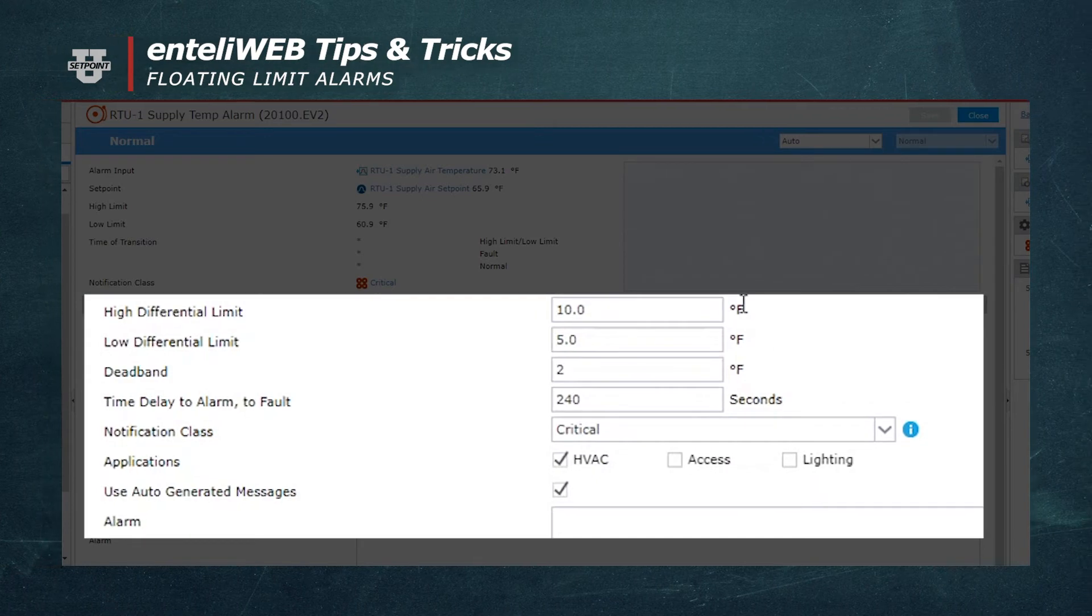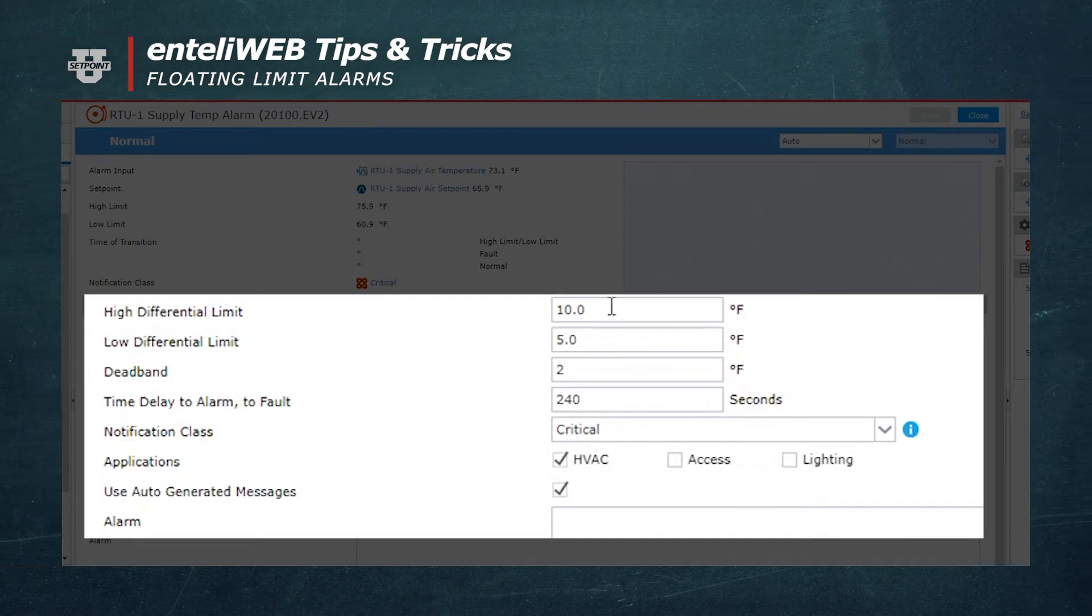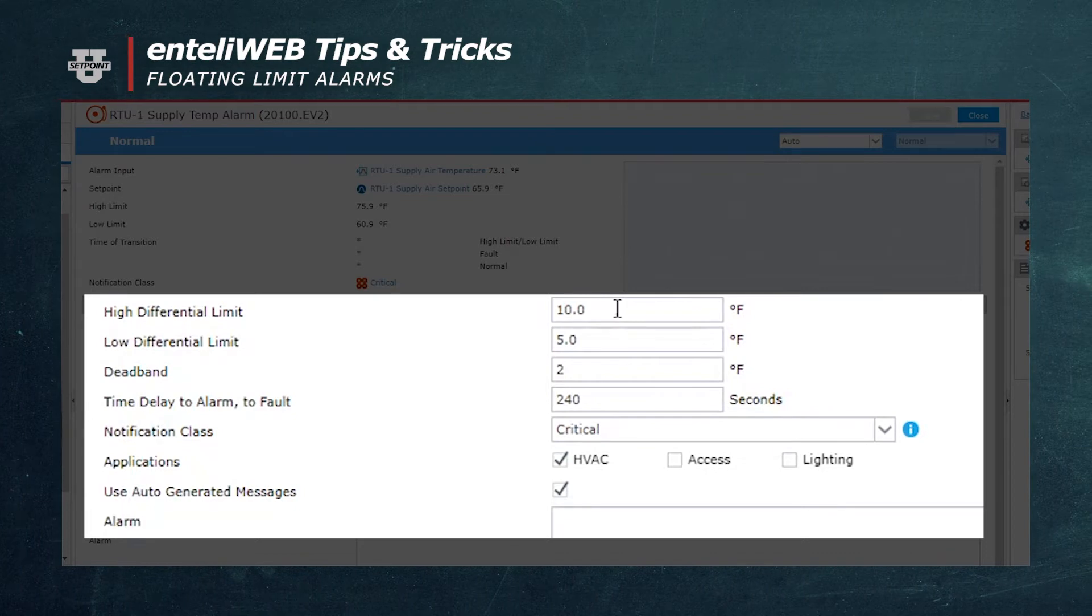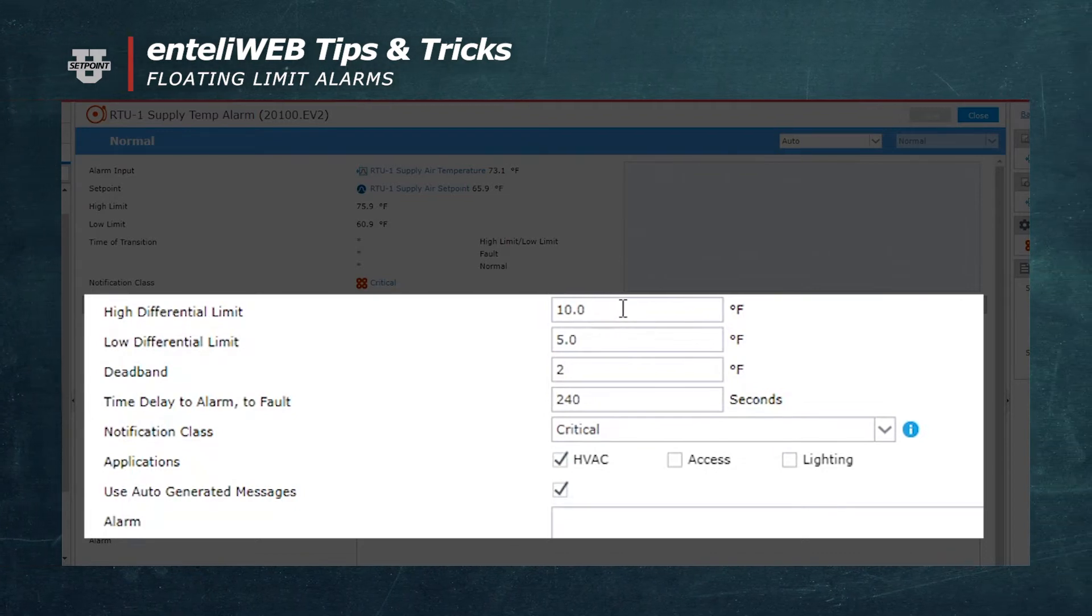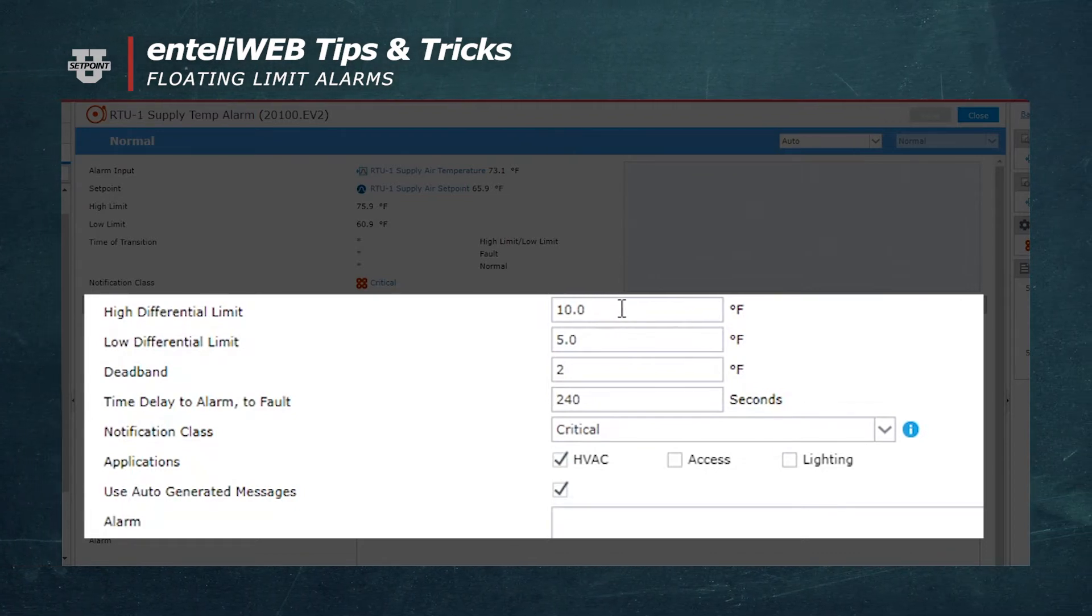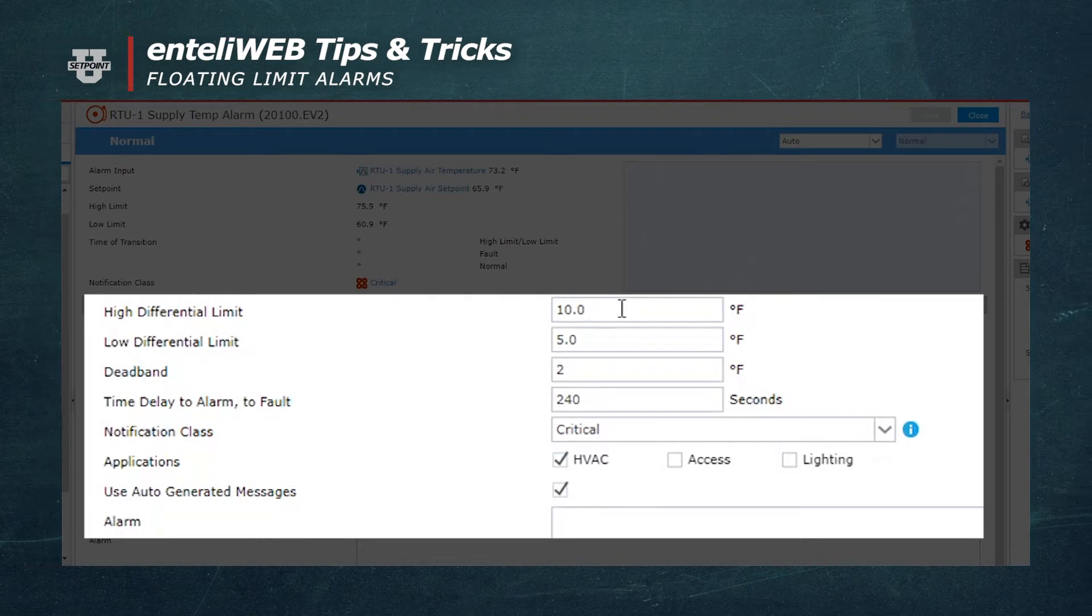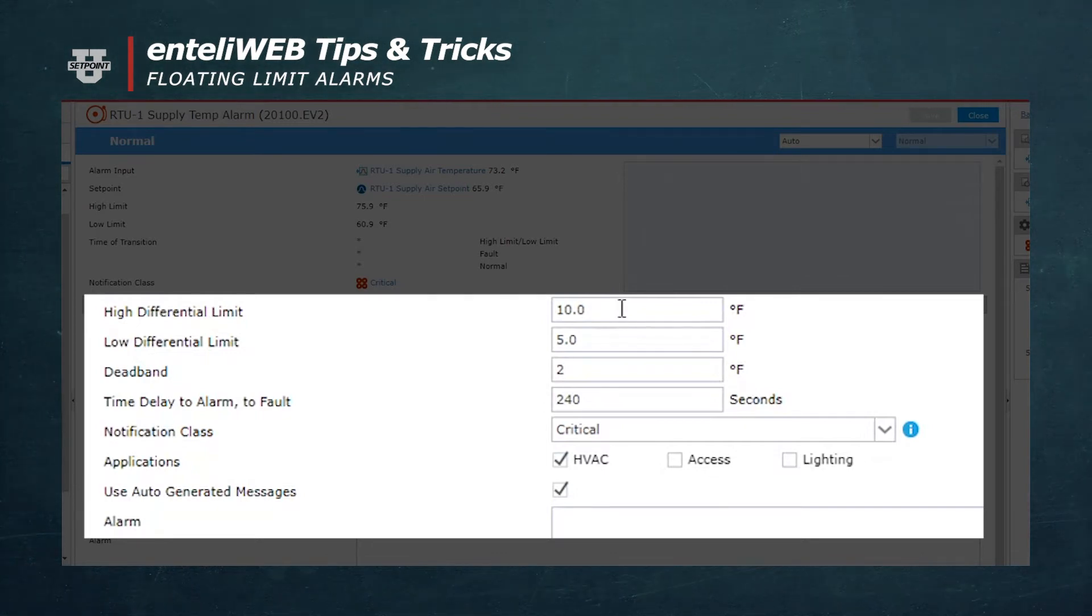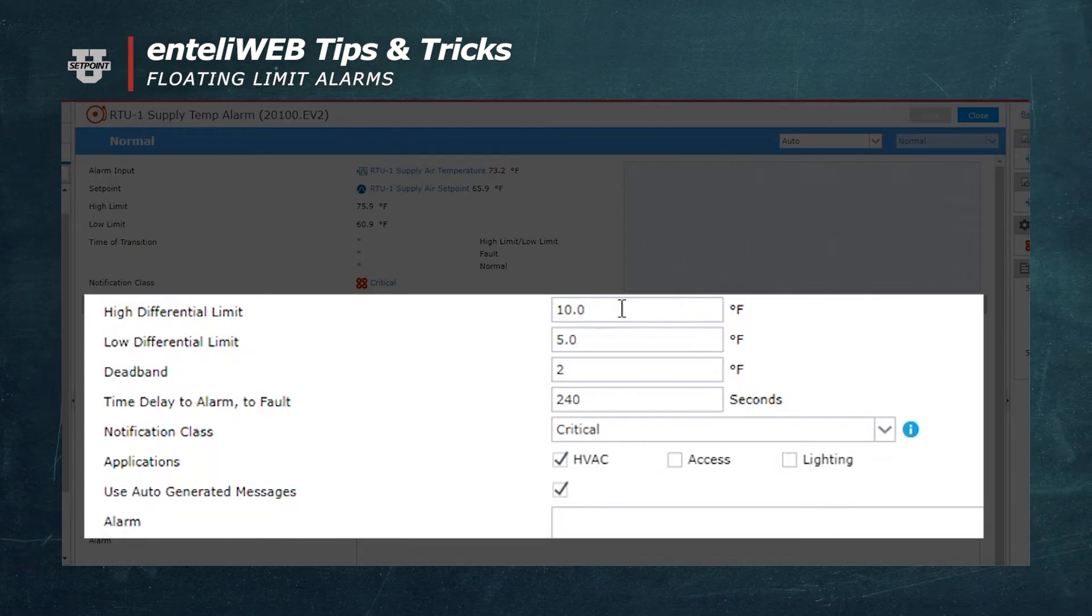Down here, the high differential limit is 10 degrees, and what this means is that an alarm would be generated when the temperature exceeded the setpoint, which is 65.9 right now, by 10 degrees. So if it got to 75.9 degrees, it would cause an alarm to take place.